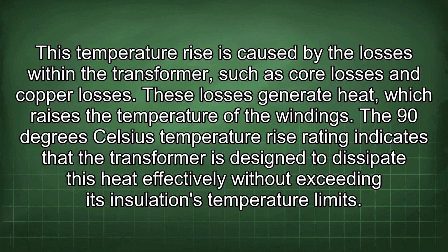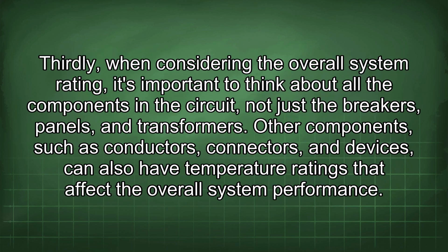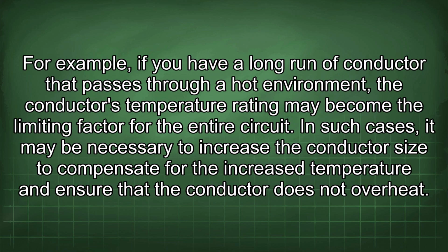Thirdly, when considering the overall system rating, it's important to think about all the components in the circuit, not just the breakers, panels, and transformers. Other components, such as conductors, connectors, and devices, can also have temperature ratings that affect the overall system performance. For example, if you have a long run of conductor that passes through a hot environment, the conductor's temperature rating may become the limiting factor for the entire circuit. In such cases, it may be necessary to increase the conductor size to compensate for the increased temperature and ensure that the conductor does not overheat.